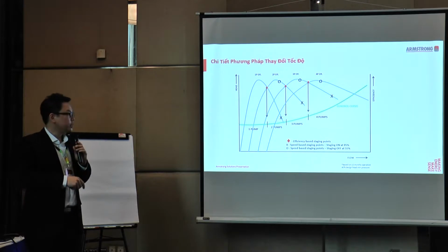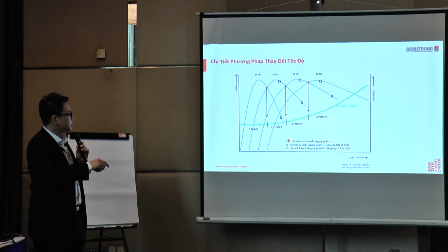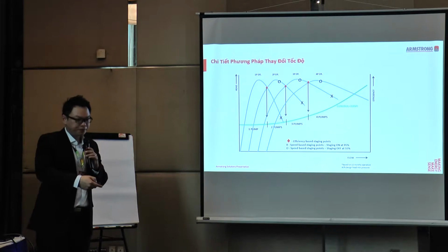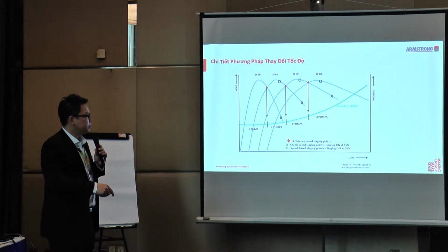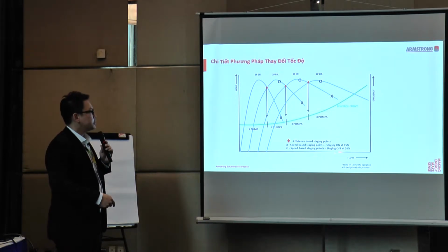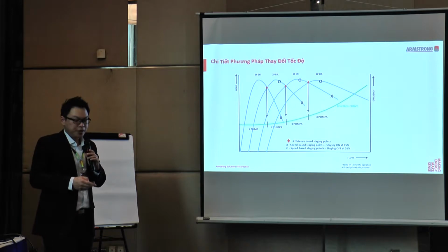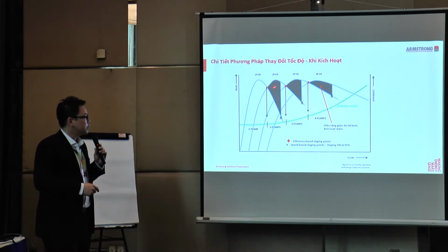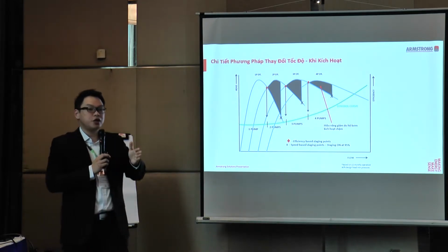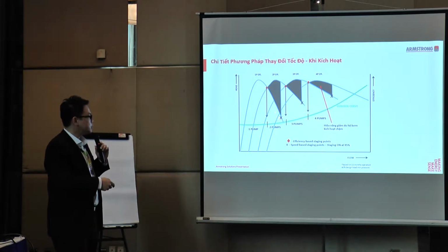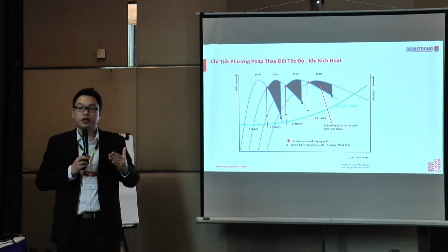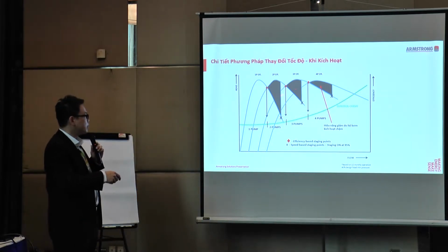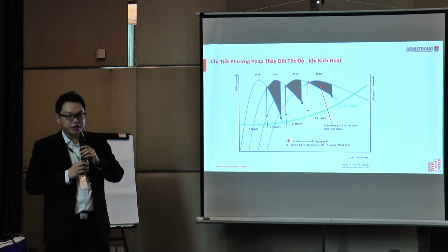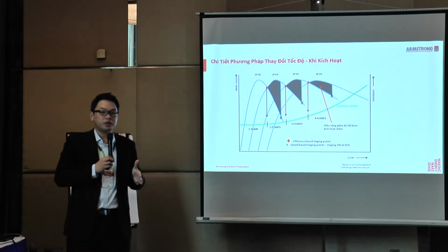Based on that graph, you will realize that for speed-based control, it would go all the way to almost 90 to 95% of the maximum speed before it turns on the next pump. So it stages on the next pump at 95% of the speed and stages off at 55% of the speed. If I do some shading here, this diamond point is where Armstrong's approach stages on the next pump. This cross is where the traditional speed-based approach will turn on the pump. These black areas, 1, 2, 3, represent the loss of efficiency due to late staging on of the next pump.